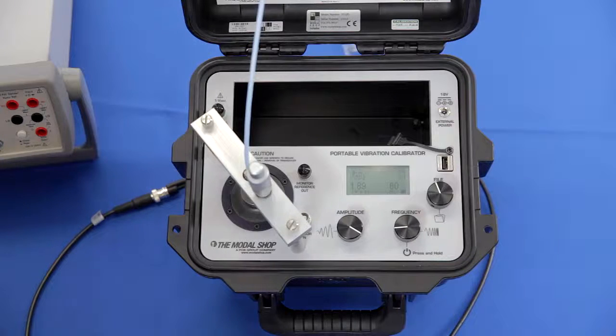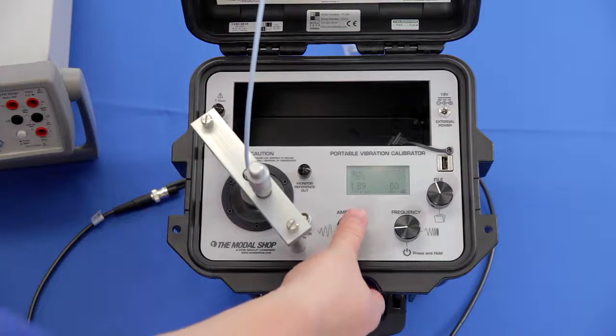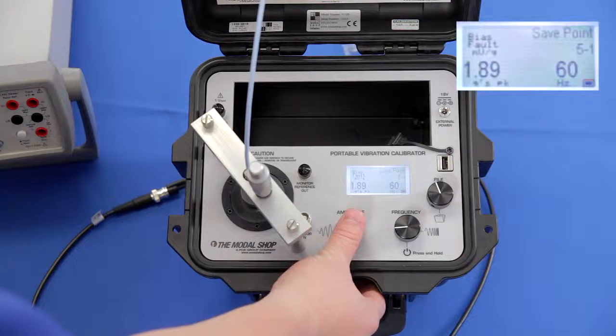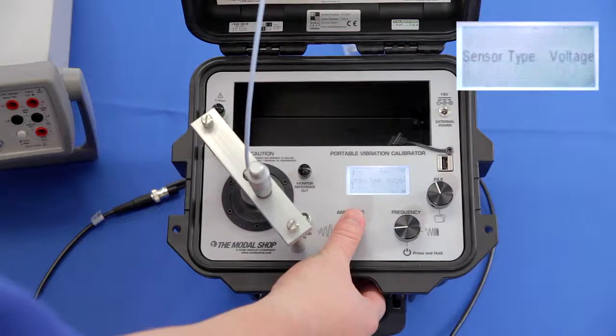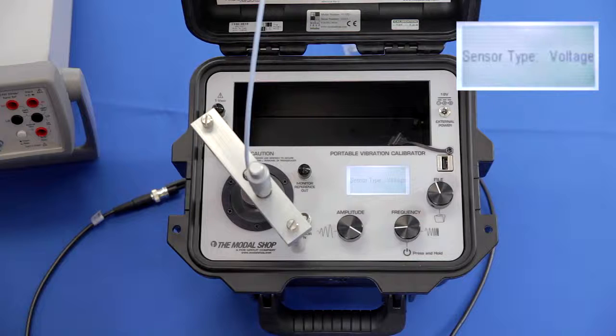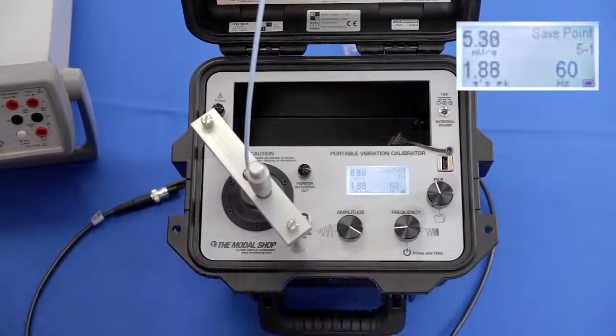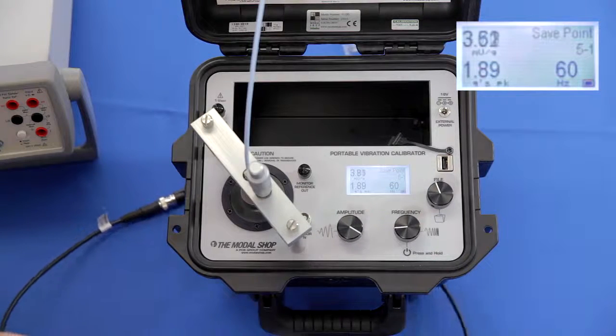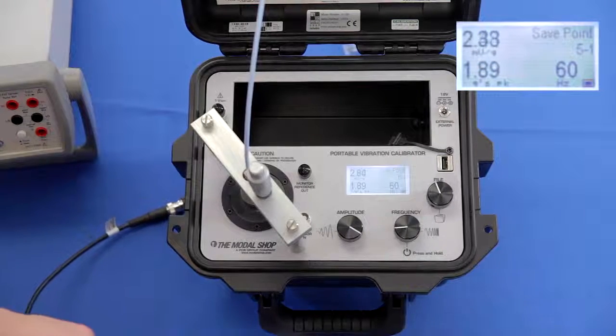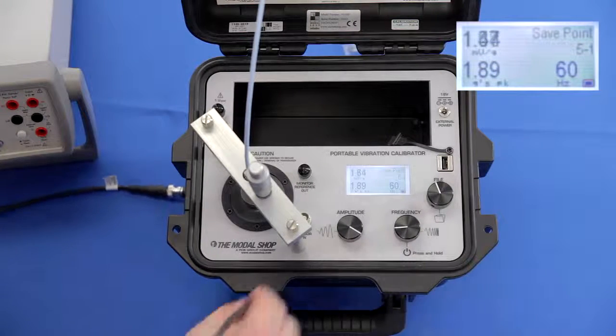So now we're ready to perform our proximity probe amplitude response calibration. The first thing I want to do is make sure my calibrator is in voltage mode. I hold down the amplitude button and I see sensor type voltage, so I'm good to go there. I can now disconnect the proximity probe from the voltmeter and connect it to the calibrator here, test sensor input.